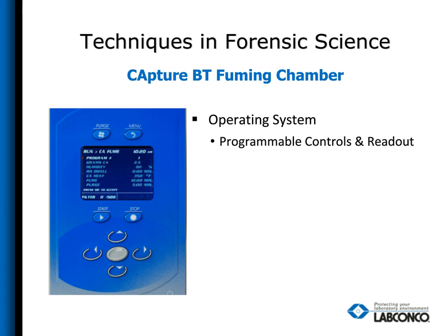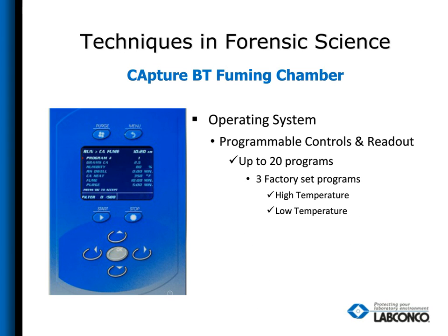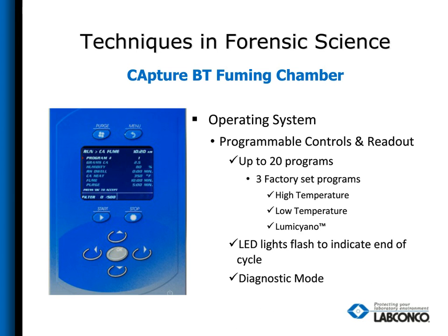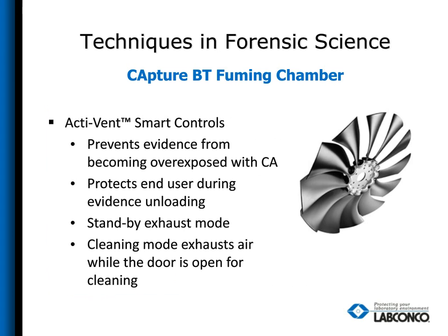Up to 20 programs can be stored in the Capture BT's operating system. The first 3 programs are set for high heat, low heat, and lumicyano, the new CA that fluoresces in the gas stage. The operating system includes a diagnostic mode that will check each function of the Capture BT in a matter of minutes to confirm proper operation and to troubleshoot if a problem occurs. LED lights will flash at the end of the cycle to give a clear indication that the cycle is complete.